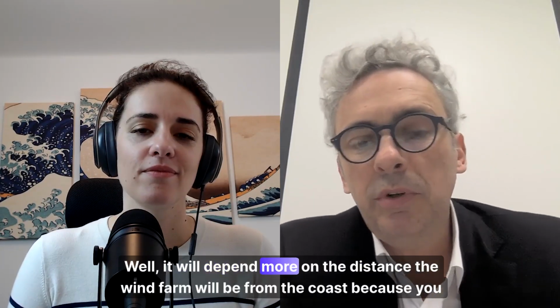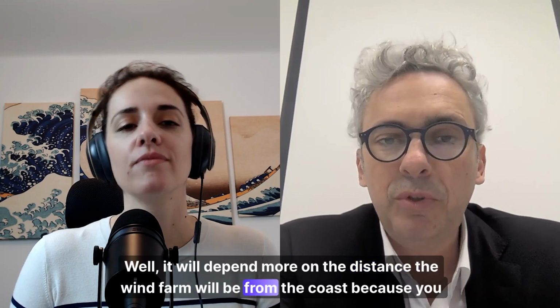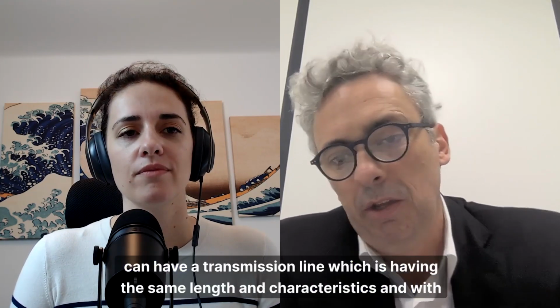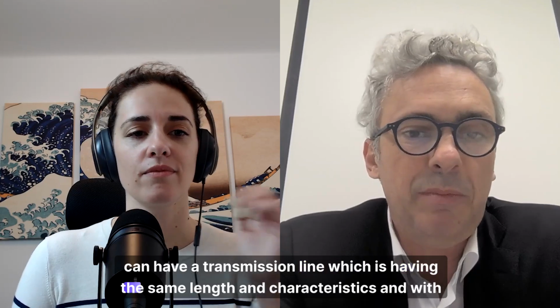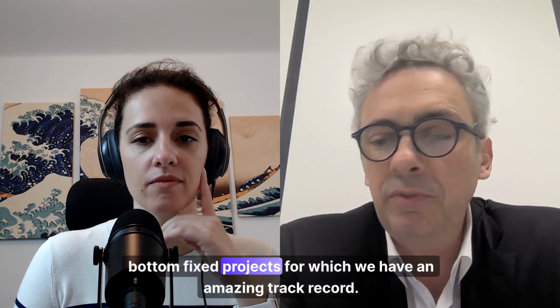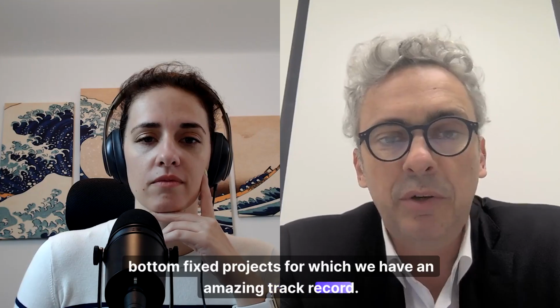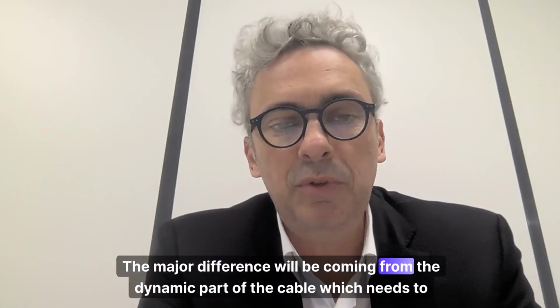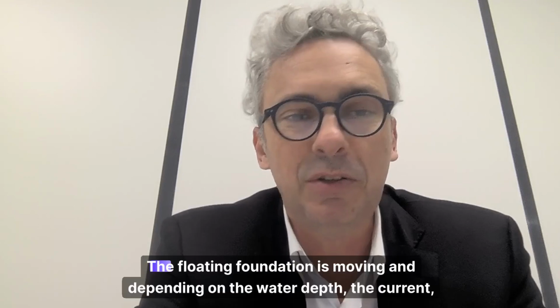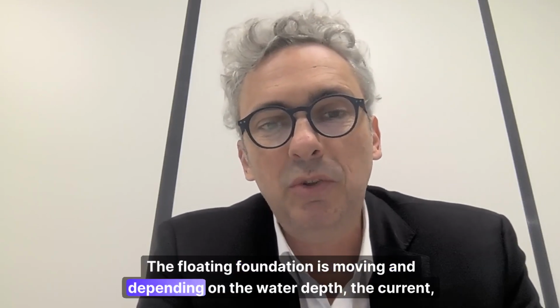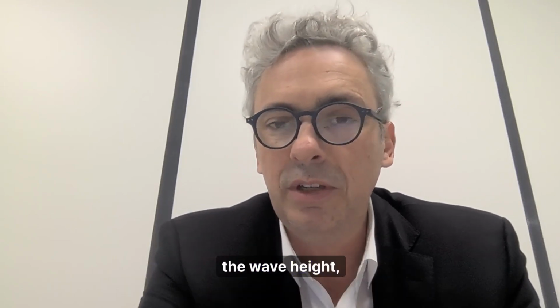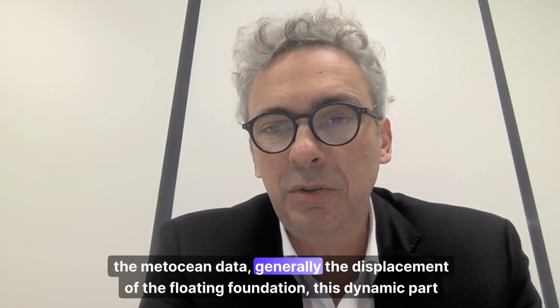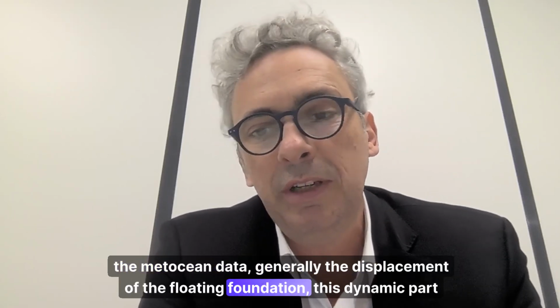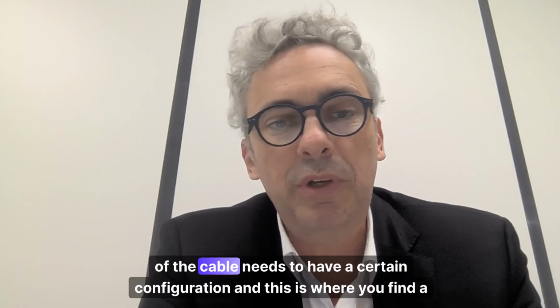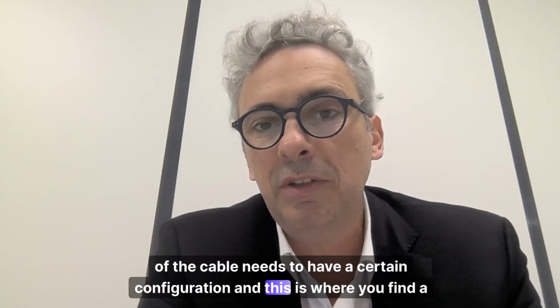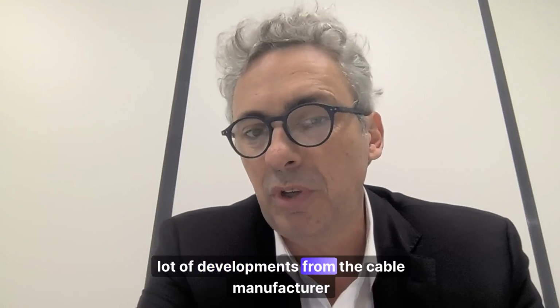Well, it will depend more on the distance the wind farm is from the coast, because you can have a transmission line with the same length and characteristics as bottom-fixed projects, for which we have an amazing track record. The major difference comes from the dynamic part of the cable, which needs to move since the floating foundation is moving. Depending on water depth, current, wave height, and the metocean data - generally the displacement of the floating foundation - this dynamic part of the cable will need a certain configuration, and this is where you find a lot of development from cable manufacturers.